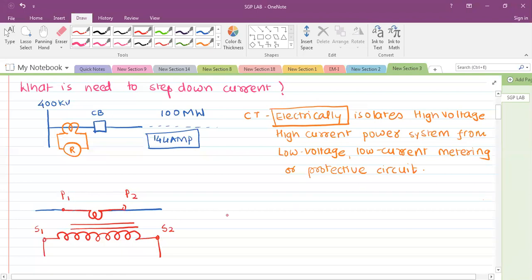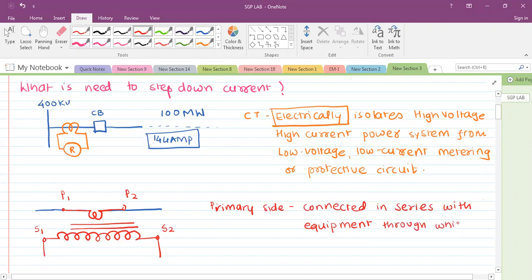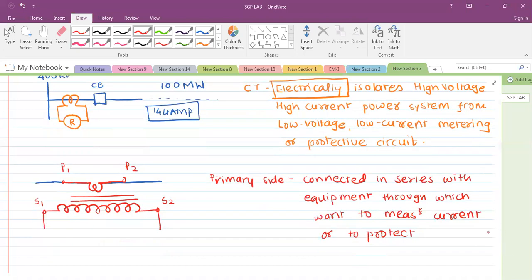And this is the actual physical connection where the primary side is connected in series with the equipment through which you either want to measure the current or want to protect. Okay, either you want it for the measurement purpose or you want it for the protection purpose.